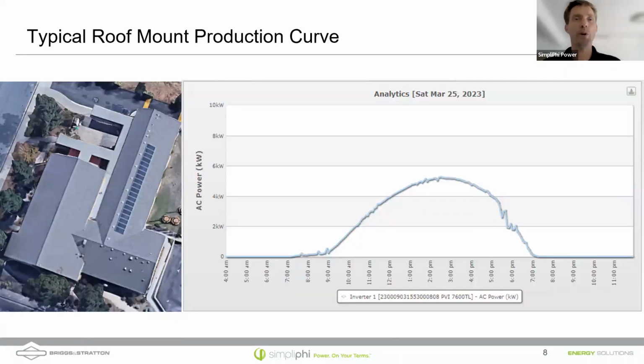So here is a typical roof mount production curve. This is actually an install that I did together with students and a local contractor - 20 425-watt panels, so an 8.5 kilowatt array. I'm showing you production out of this array back in March. If you look at that, that's an 8.5 kilowatt array, a little over 8 kilowatt array, and what you'll notice is that it peaks out at less than 6 kilowatts of AC production. I'm going to get into why that is the case today and talk about how we can use batteries to generate more power.